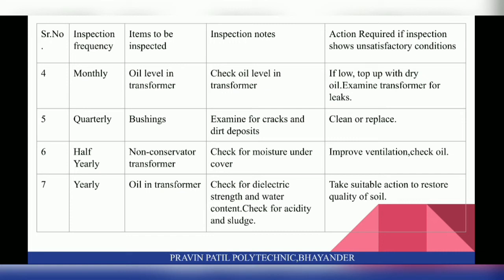For half-yearly basis, check the non-conservator transformer for moisture under the cover. Action required: Improve ventilation and check oil. For yearly basis, check oil in the transformer for dielectric strength, water content, acidity and sludge. Action required: Take suitable action to restore quality of oil.